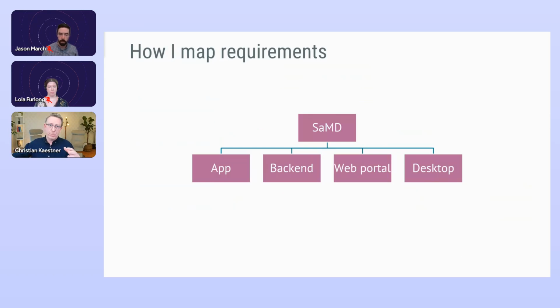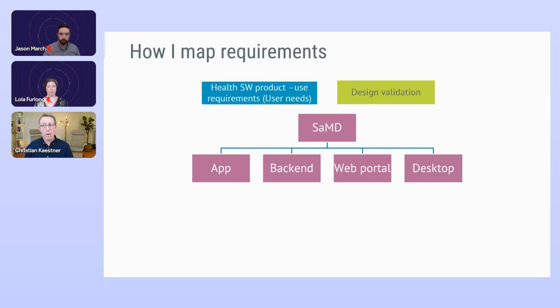To give you another perspective on this, I can share how I would map requirements in a structure like this. So we have a SaMD device with an app, backend, web portal, and desktop. I will start at the top by defining user needs. If you're familiar with IEC 82304-1, that's in that standard, it's called use requirements. I will use the user needs to design a design validation to see if the users can do what I want to achieve with the product.